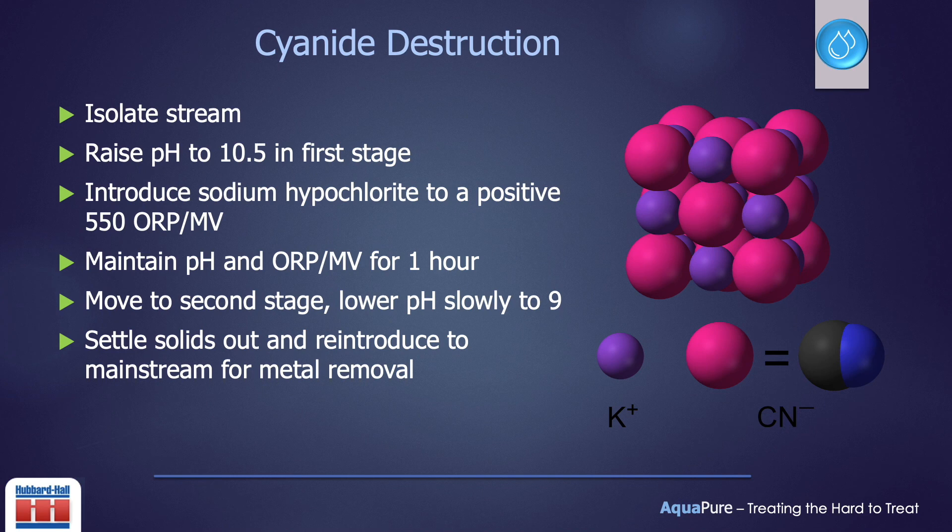Alkaline chlorination for cyanide destruction is the most common practice used in the metal finishing industry. It can be dangerous if not completed properly. The cyanide stream is isolated for the destruction process. Alkaline chlorination is a two-step process. The first step is the formation of cyanogen chloride at a high pH of 10.5 or higher. Sodium hypochlorite is introduced to achieve a positive 550 ORP reading. While maintaining the high pH and ORP reading, the solution is allowed to mix for up to one hour, allowing the cyanogen chloride to form cyanate. The second step is to lower the pH to 8.5 or 9, which converts the cyanate to ammonia and carbonate. Once the second stage is complete, solids will form. Allow them to settle out before returning the wastewater to the mainstream for metal removal.